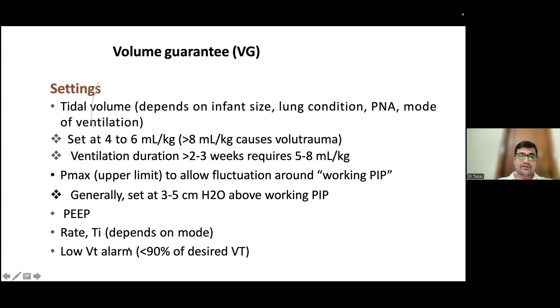You have to set the PEEP, then the rate and TI depending on the mode of ventilation. Like in case of SIMV, you have to set the rate and TI. However, it is not required in case of PSV or assist control ventilation. Then you have to set the low VT alarm. Typically the low VT alarm, or low tidal volume alarm, is set at less than 90% of the desired tidal volume.